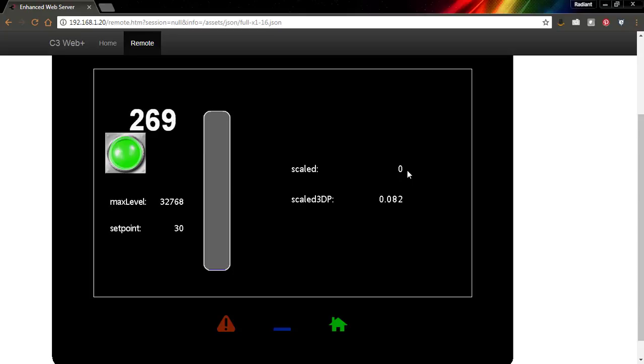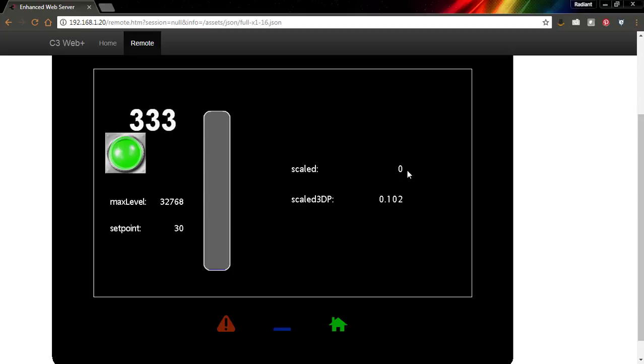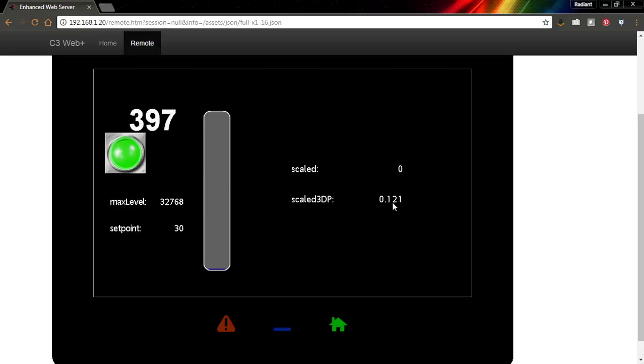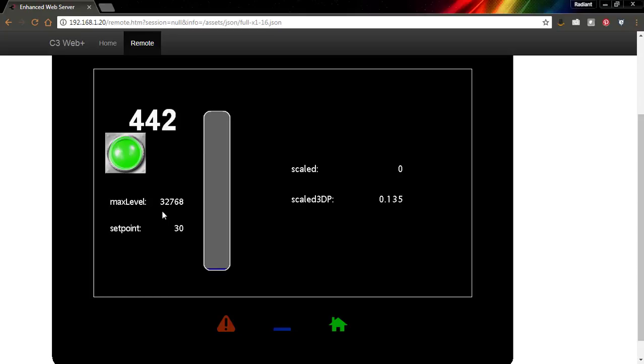It's going to take a long time before we see the non-decimal place value start to change. That's because we've essentially given this scaled tag only 10 data points it can choose from for values ranging from 0 to 32,767. That's where adding decimal points is valuable. You can also see the primitive immediately adapted to that new max level.